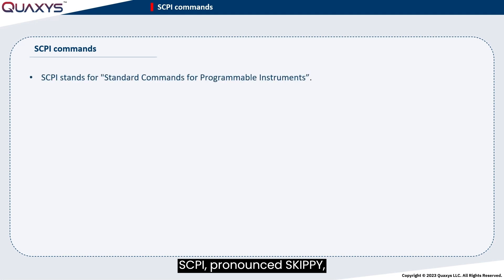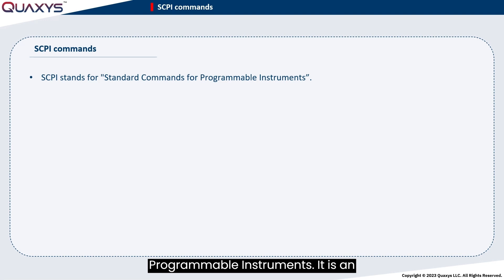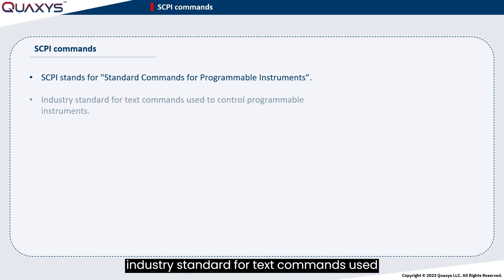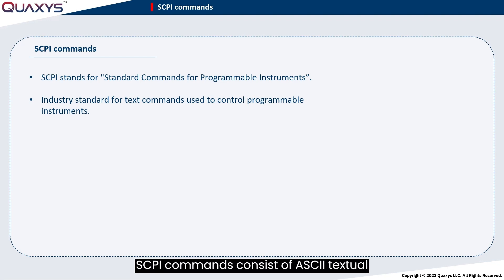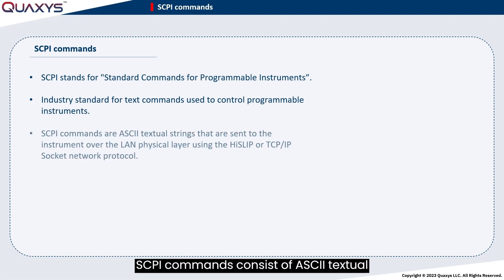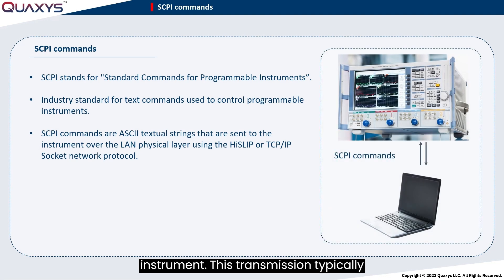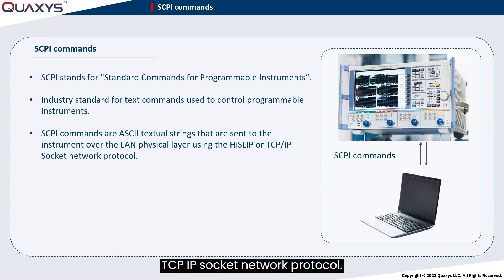SCPI, pronounced 'skippy', stands for Standard Commands for Programmable Instruments. It is an industry standard for text commands used to control programmable instruments. SCPI commands consist of ASCII textual strings that are transmitted to the instrument. This transmission typically occurs over the LAN physical layer, utilizing protocols such as HiSLIP or TCP/IP socket network protocol.